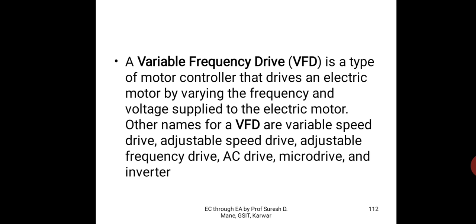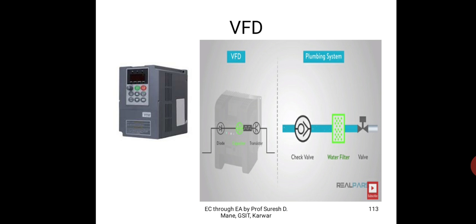Synchronous speed ns is equal to 120 into f, that is frequency, divided by p, where p is the number of poles. Number of poles is fixed, the only thing I can change is frequency, so by changing frequency I can change the speed, and this is done by VFD. It is used in pumps also, and wherever motors are used, VFDs are used — for lifts, AC, fridge, everywhere a motor is used, VFD can be used.